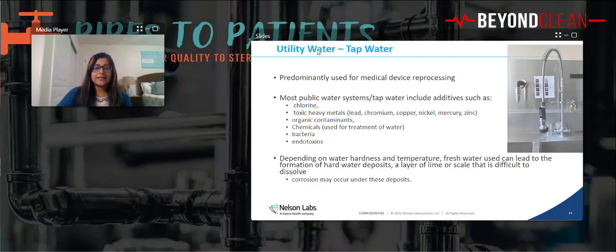Chemicals, bacteria, endotoxins. Depending on the water hardness and the temperature, water can lead to a lot of lime scale and corrosion. And so it's very important to understand that all of these things that I just mentioned are in your water, in your utility water. And all of those do contribute to patient safety, right? We want to make sure that we're using the right water. Now, this is the beginning side of processing, so cleaning validation. We still have 2 more steps to go through. So using this water up ahead may be okay, but you still have to monitor to make sure that the water systems are at lower limits per standards, and so they don't contribute to further degradation as they go on.